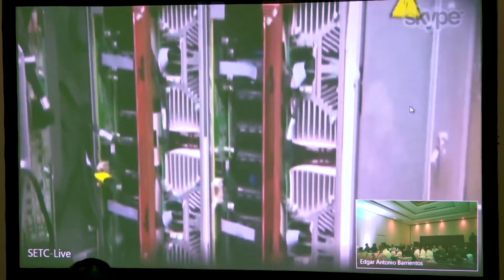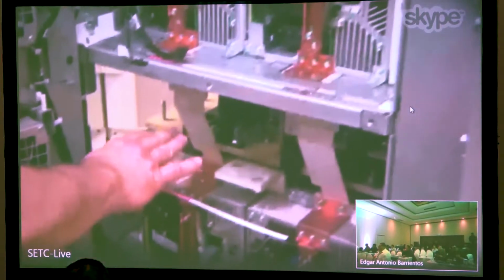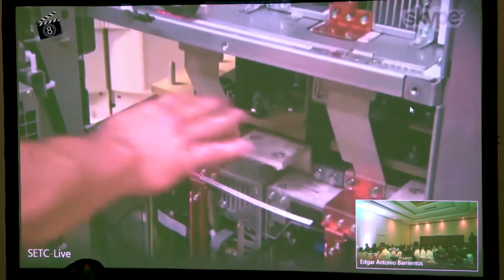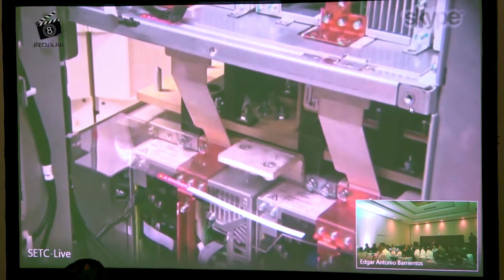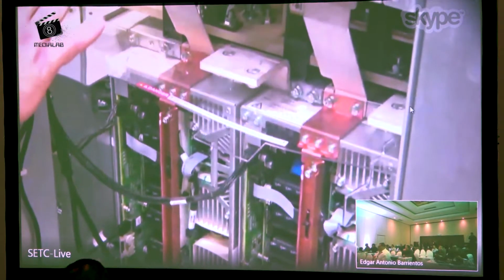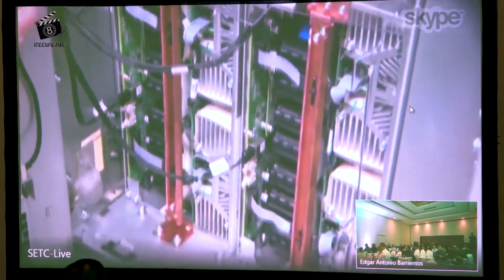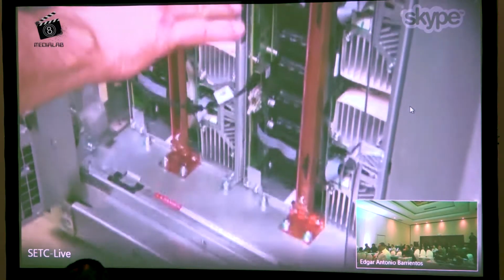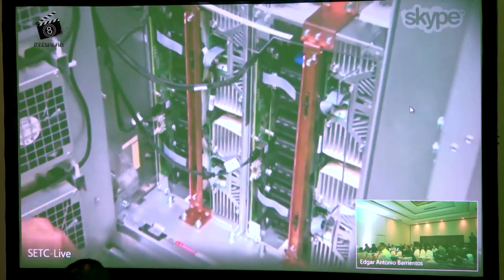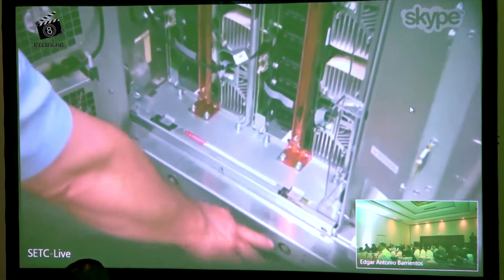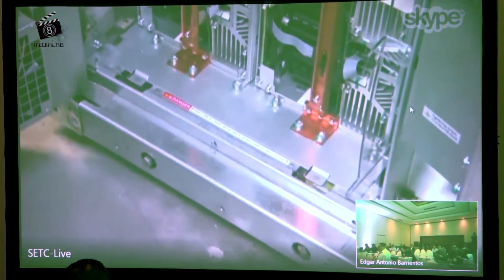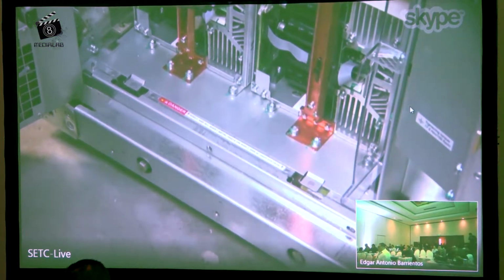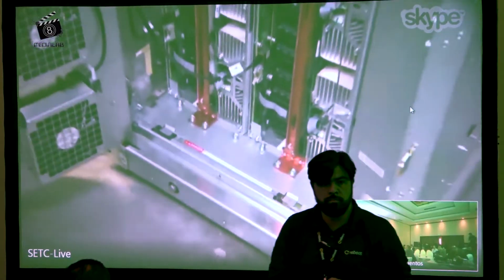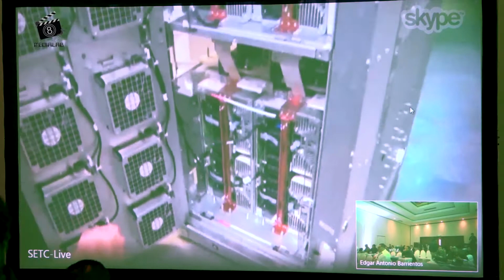This is phase B of the power blocks. Moving down a bit more, we see the inter-bus connections that go cabinet to cabinet, from power cabinet to power cabinet to the input-output cabinet. This is phase C of the power blocks. At the very bottom, there are bolts that go all the way through the cabinet and seat into brackets that anchor the cabinet and UPS to the floor.